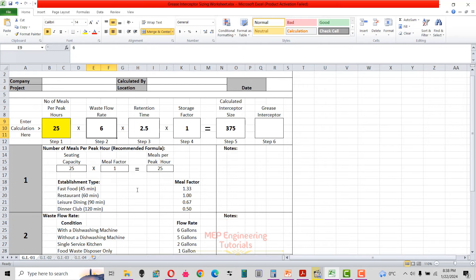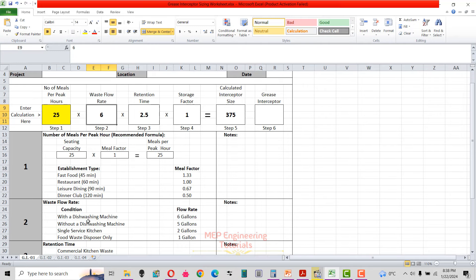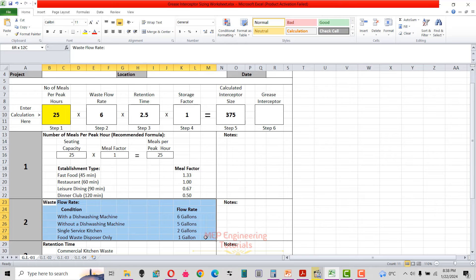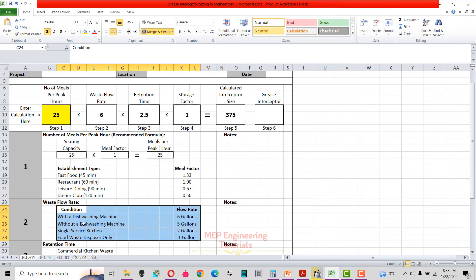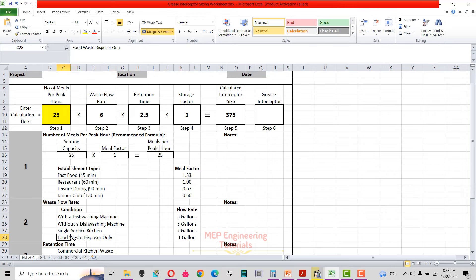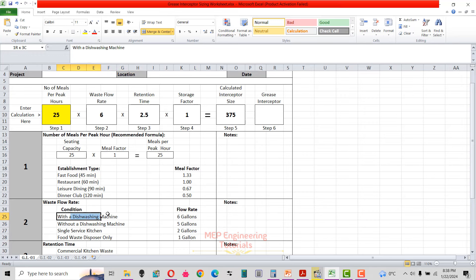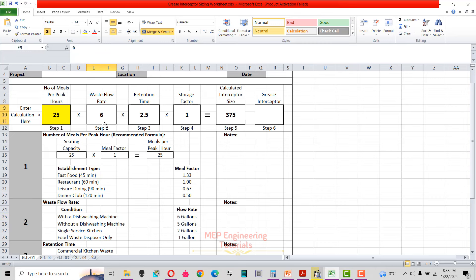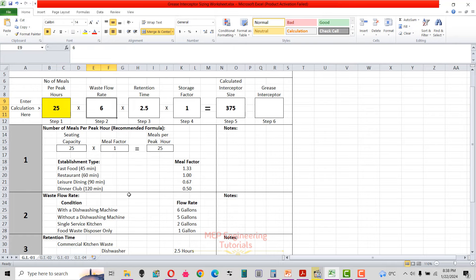Step 2: get the waste flow rate. As per the Uniform Plumbing Code, there are four conditions — with dishwashing machine: 6 gallons; without dishwashing machine: 5 gallons; single service kitchen: 2 gallons; food waste disposer only: 1 gallon. Since we are using a dishwashing machine, our waste flow rate is 6 gallons.